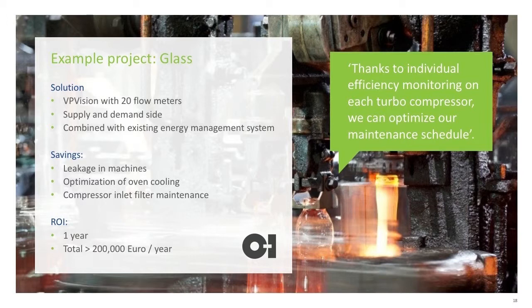Also in this case, they had some turbo machines, centrifugal machines, which sometimes had clogged inlet filters because of the environment. And by placing flow meters at each compressor, each centrifugal machine, they were able to track that and to see when the compressor would perform less, and then they would simply change the filter on time. In this way, they were able to optimize the maintenance schedule. And the return on investment on the initial monitoring solution was less than a year. And the total amount was also quite interesting, in excess of a couple of €100,000 a year.